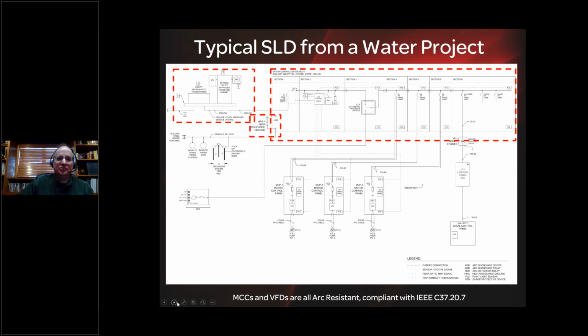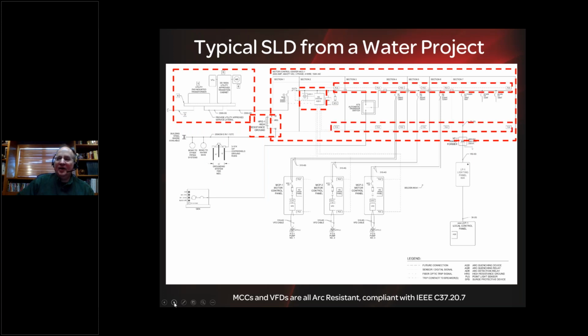So here we see the motor control center labeled MCC1. Okay. Here we see the arc quencher and the arc quencher controls installed inside the motor control center. Here I've put dashed lines over the PLS or point light sensors that are installed in this motor control center. Now, again, we could have used as well fiber light sensors. Fiber light sensors, though, do have a weakness. They don't easily support shipping splits, whereas the point light sensor, which is electrically connected, easily terminates to terminal blocks and supports shipping splits so that we don't have to install the fiber light sensors at the job site.